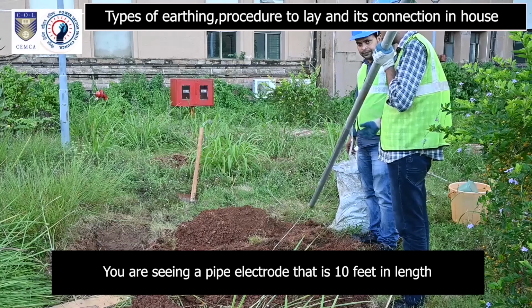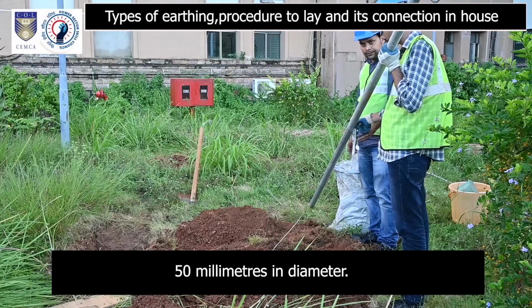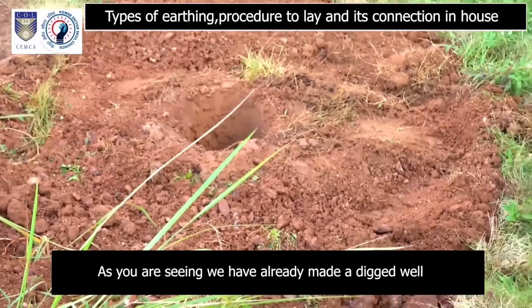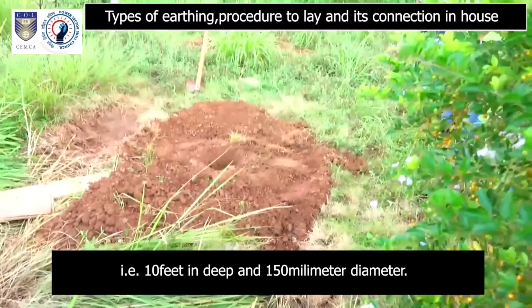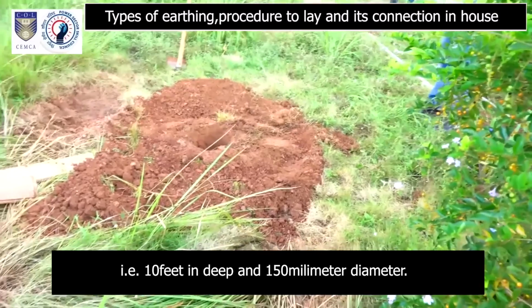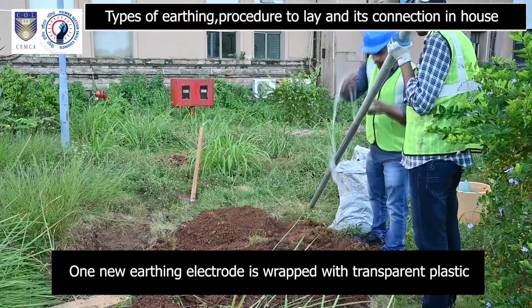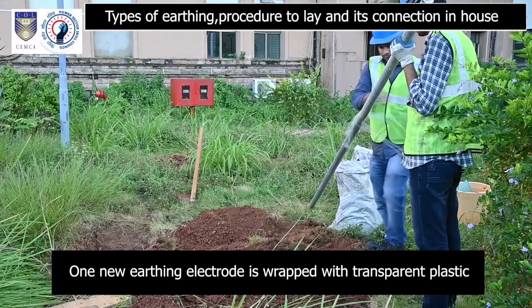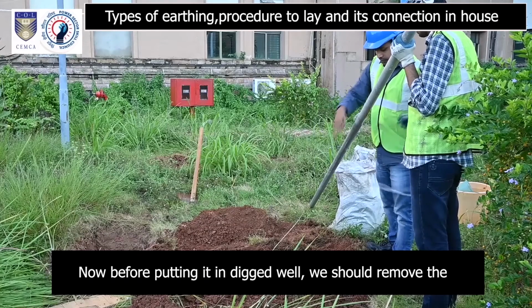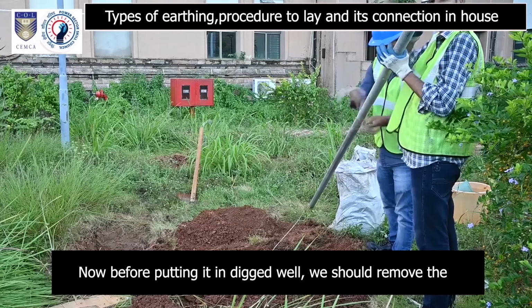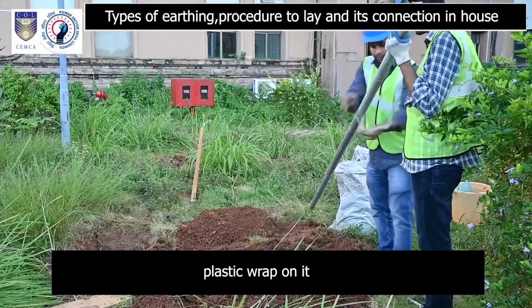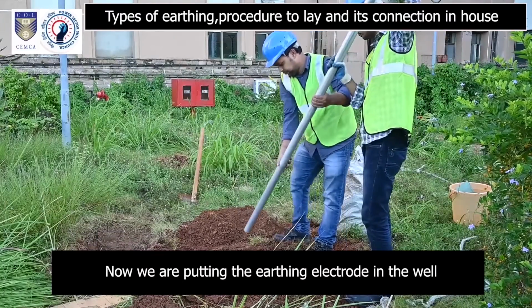You are seeing a pipe electrode that is 10 feet in length and 50 millimeters in diameter. As you are seeing, we have already made a dug well that is 10 feet deep and 150 millimeters in diameter. One new earthing electrode is wrapped with transparent plastic. Now before putting it in the dug well, we should remove the plastic wrap on it. Now we are putting the earthing electrode in the well.